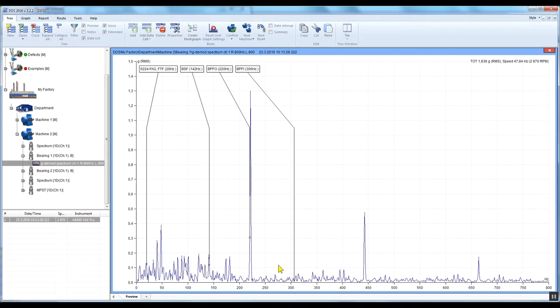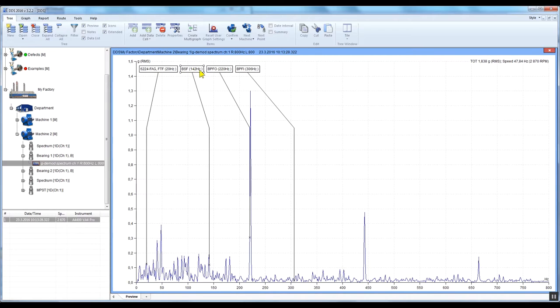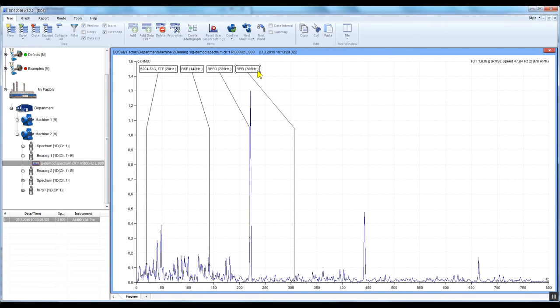The bearing fault frequencies of the defined bearing type are displayed now. We can see the type of our bearing, the fundamental train frequency (also known as the frequency of the cage), the ball spin frequency, the ball pass frequency of the outer race, and the ball pass frequency of the inner race.